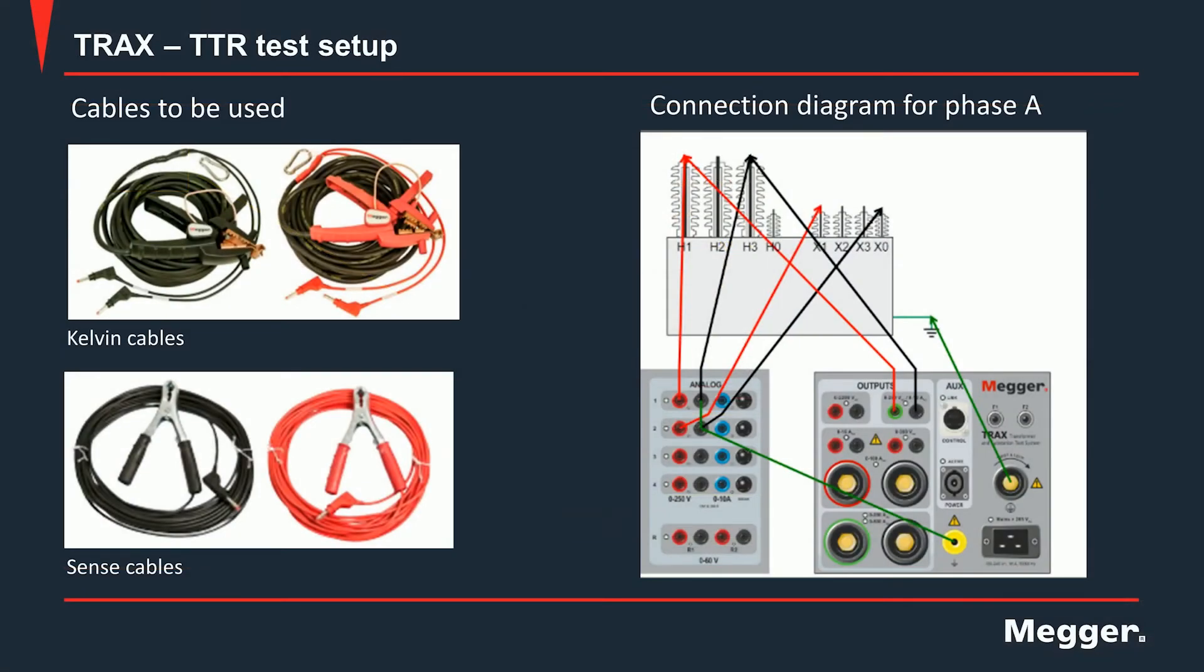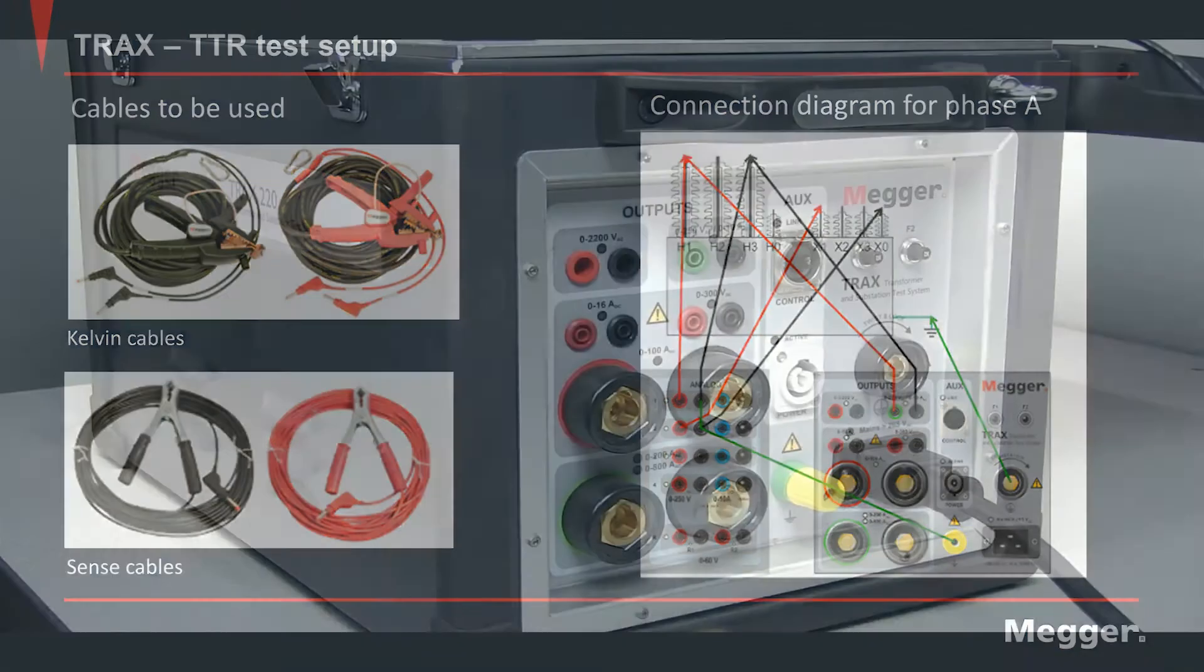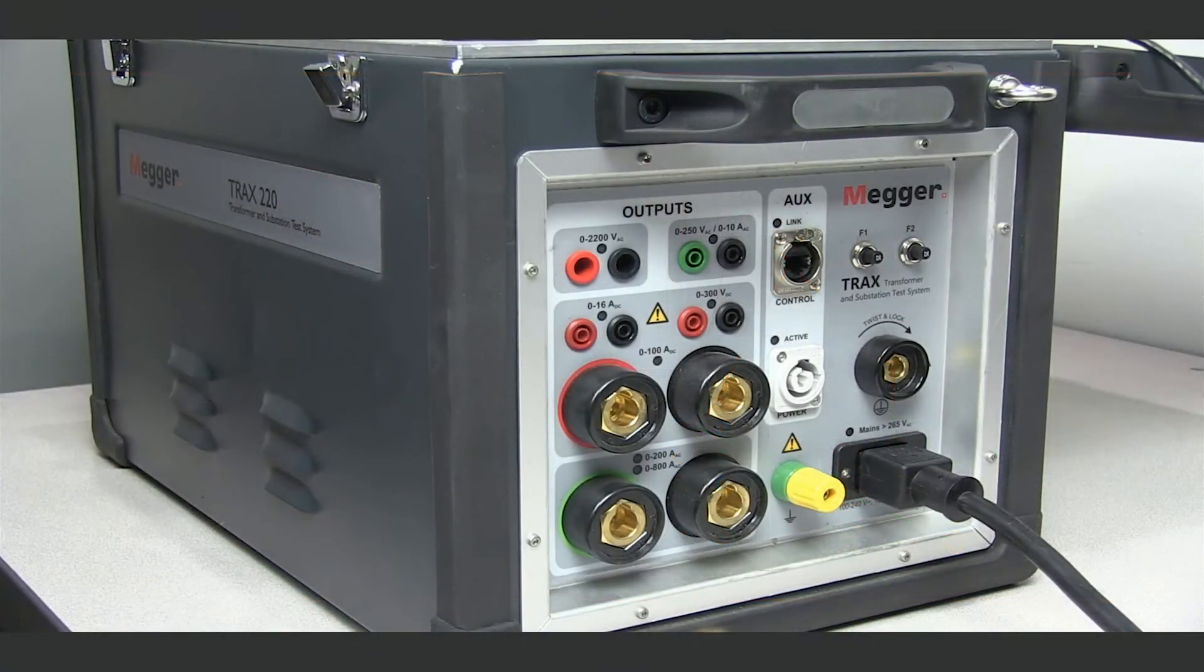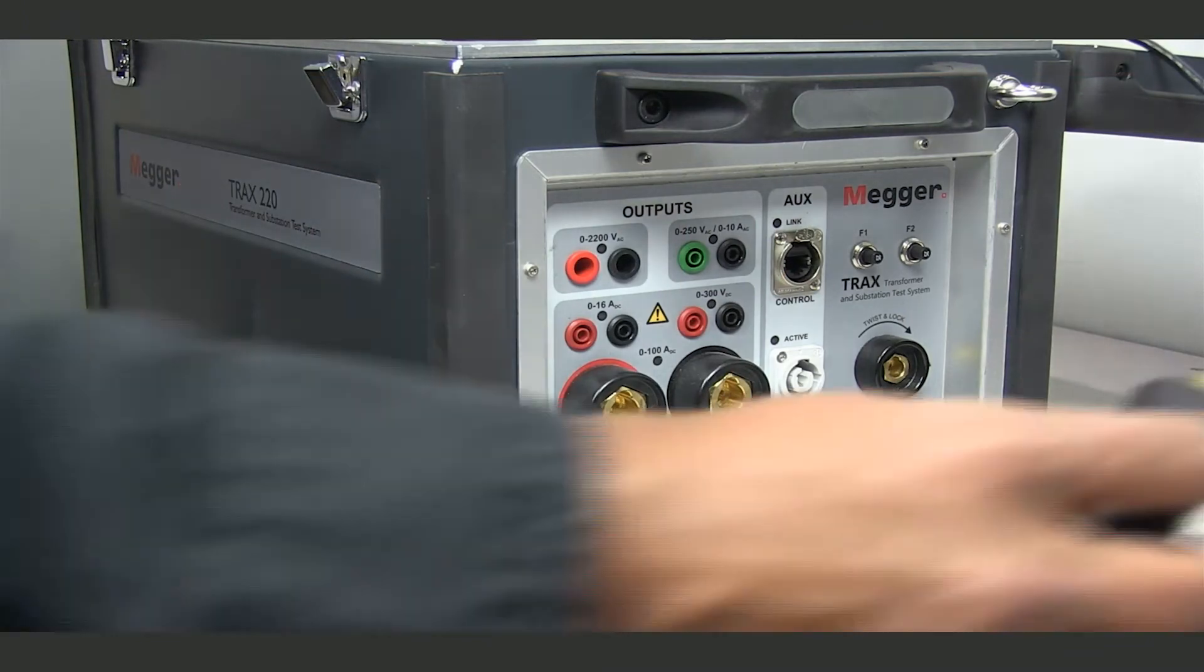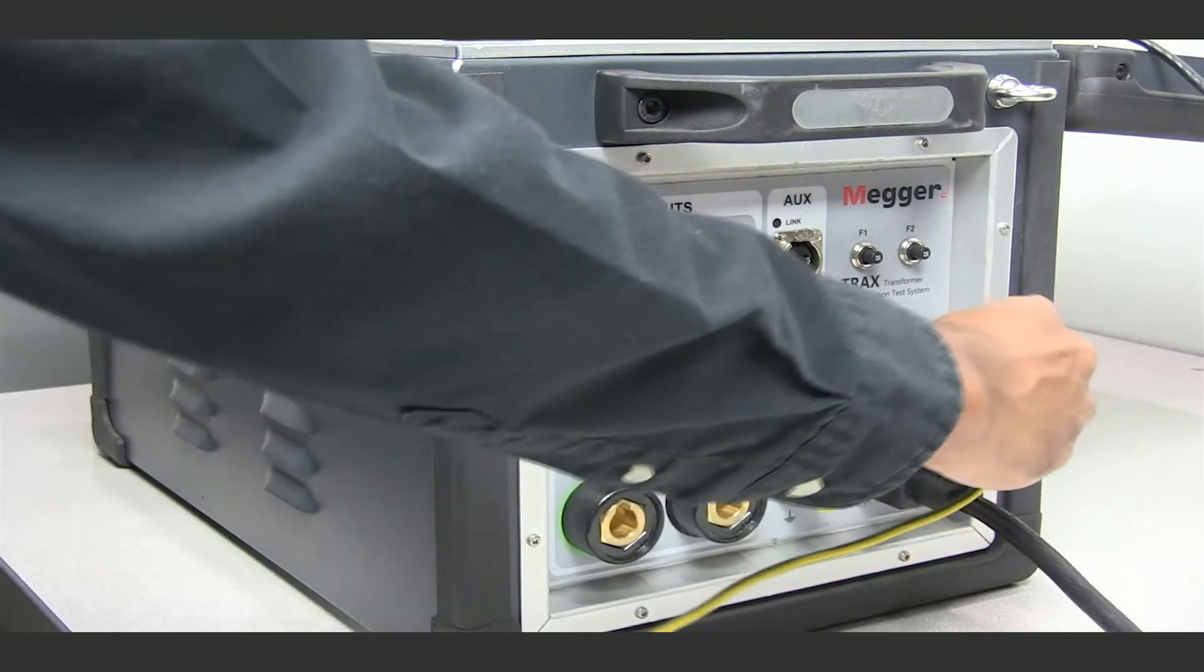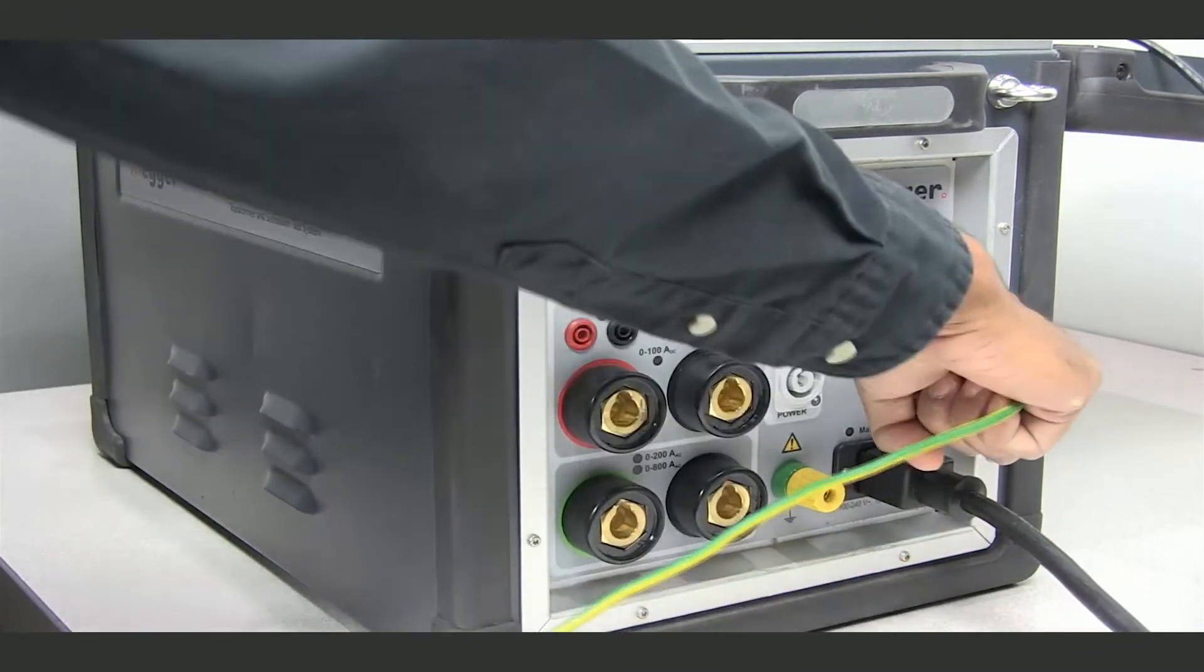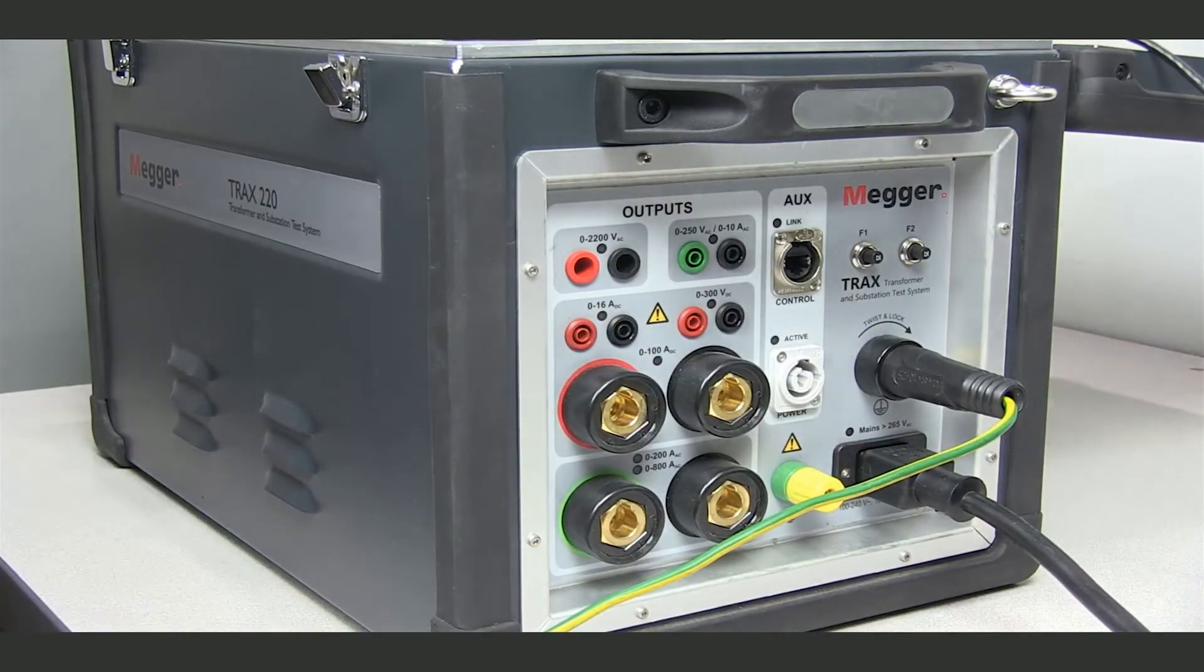To run the turns ratio test without a switch box, we need to use a pair of Kelvin cables and a pair of sense cables. The Kelvin cables would run from the TRAX to the high voltage winding and the sense cables are connected from the TRAX to the low voltage winding. The very first step is to run the ground lead from the TRAX main unit to the ground of the transformer under test.